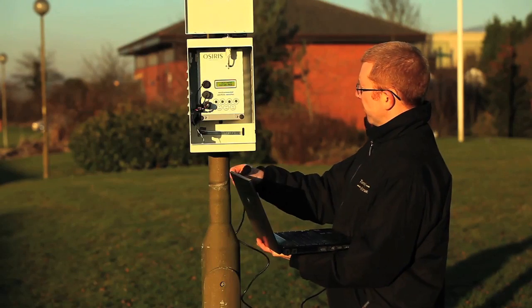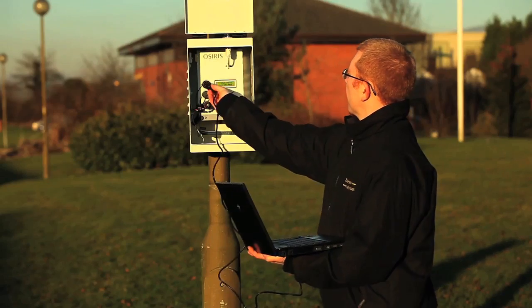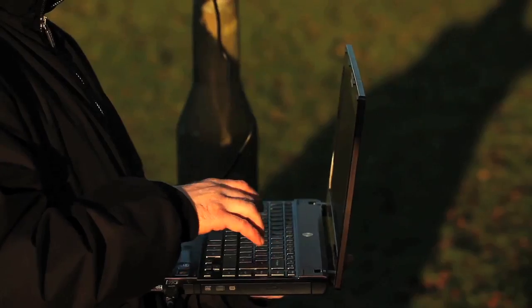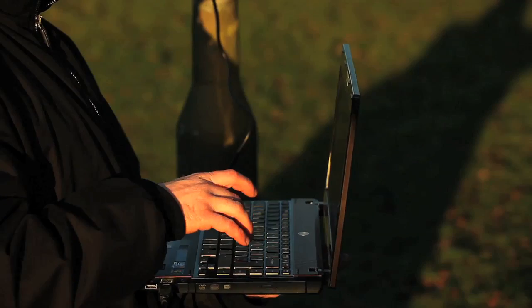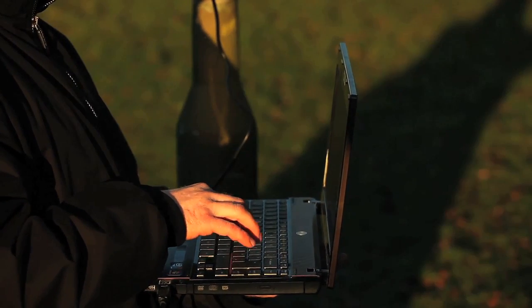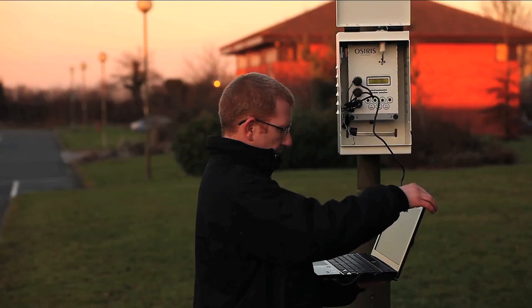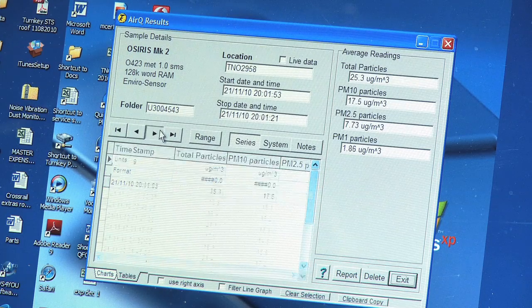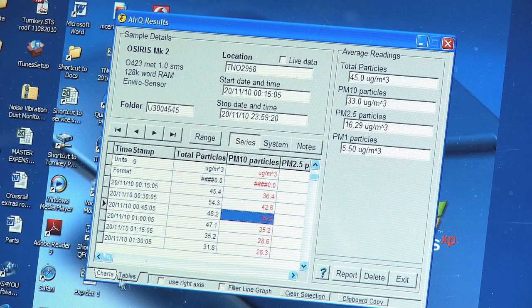The OSIRIS can log all the incoming data to its onboard memory until required. Once the information is needed, simply plug the provided link lead into a computer via the local interface and use the dedicated Turnkey AirQ program to upload all the information. Alternatively, the OSIRIS can be dialed remotely using a GSM cellular modem.